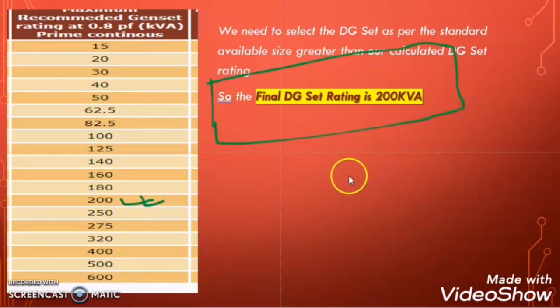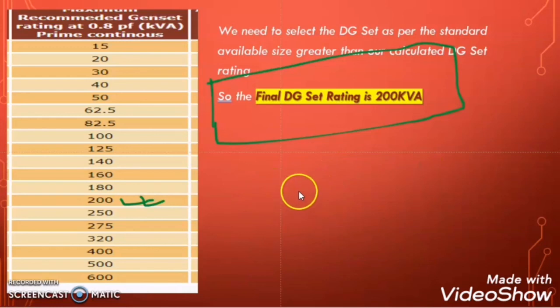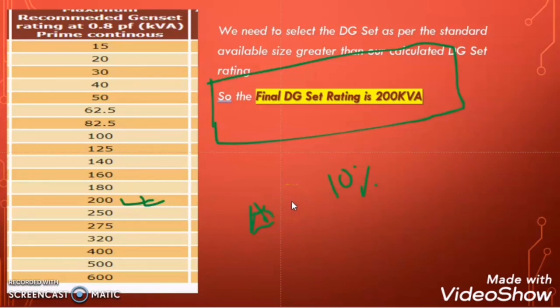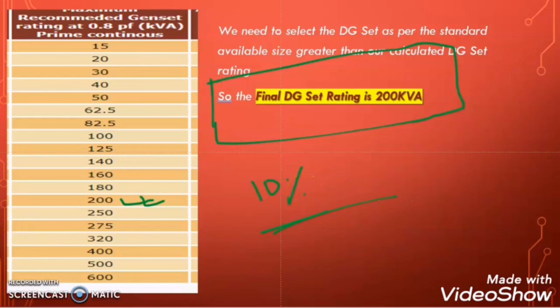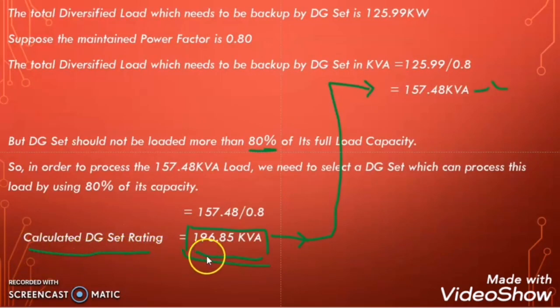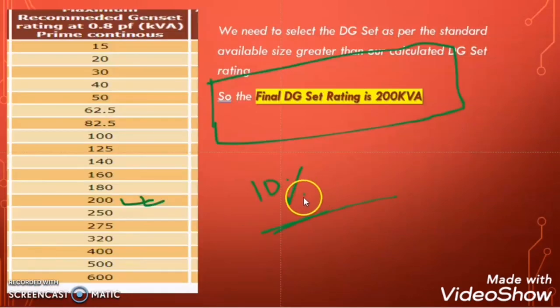One important point: a DG generator is a one-time investment, so we must consider future load extensions, as we cannot replace the generator for a small increase in load — it is very costly. If there is a chance for load extension in the future, we can consider adding 10% as a future load extension on the total calculated DG set rating. This is only applicable if there is a chance of future load extension.